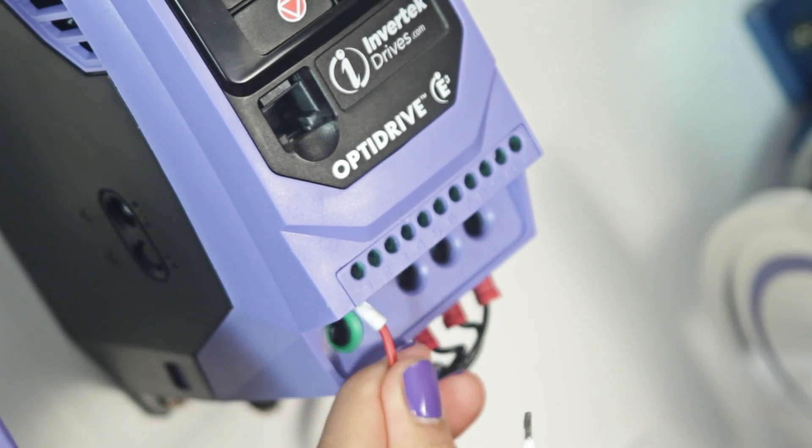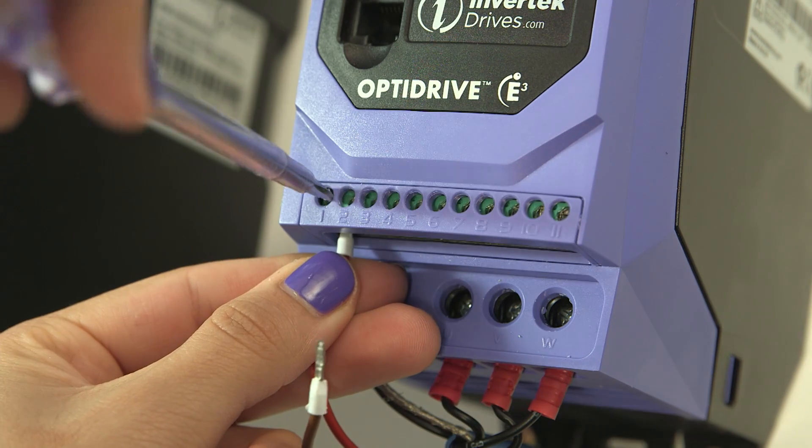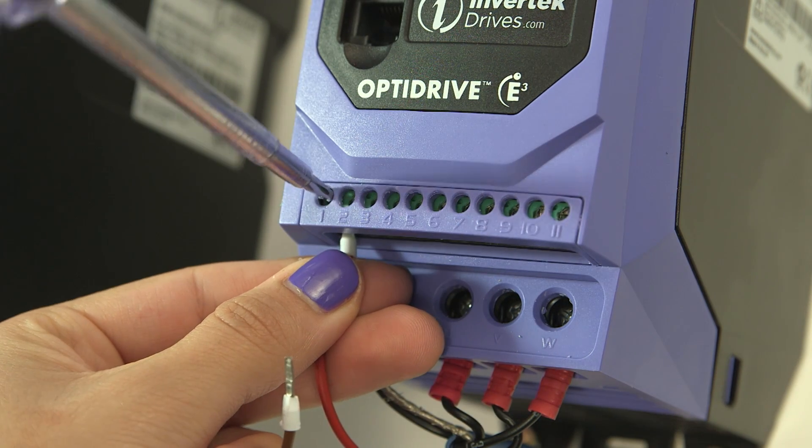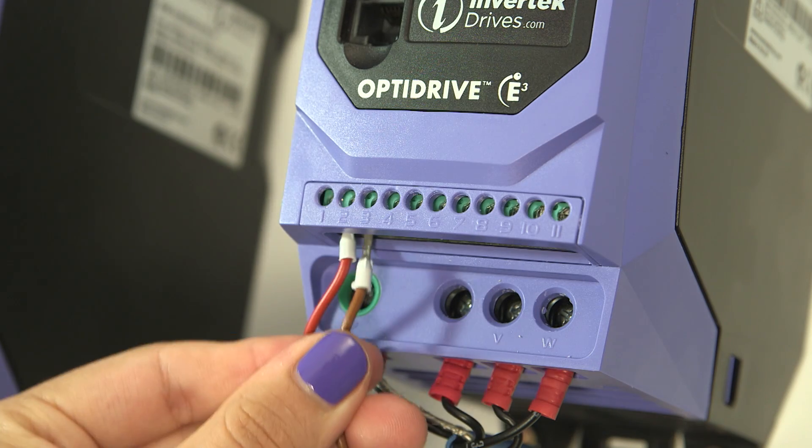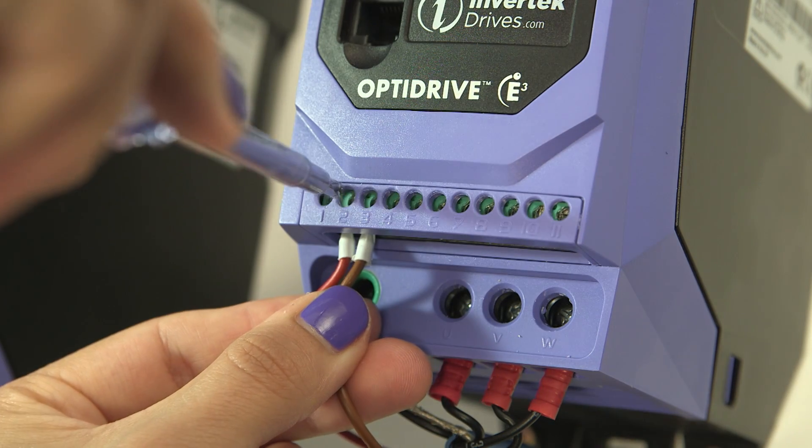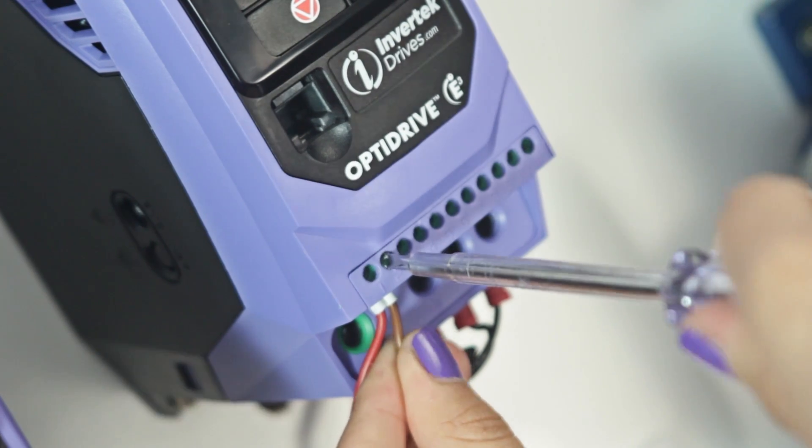Now for the controls. Connect an enable switch to terminals 1 and 2. You always need to make this connection even if you are controlling the drive from the built-in keypad or from a serial link. A simple wire link can be fitted if necessary.